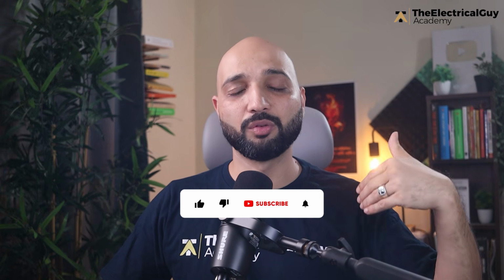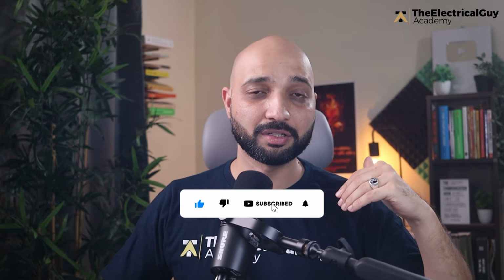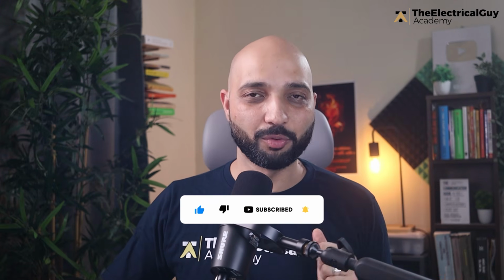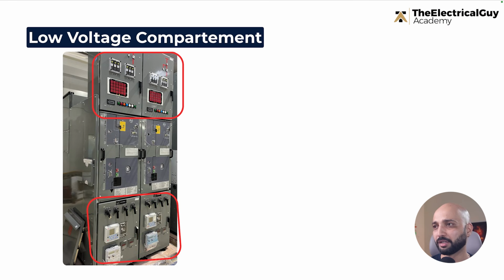So in most cases, the low voltage compartment will be different from one customer to another, one manufacturer to another. In fact, it is even different from one project to another, even if the customer is the same, right? So this may change. There is no standard rule or thumb rule that the low voltage compartment will look like this, or will have only this type of equipment. There is no such limitation. But in this video, I'll try to give you some of the common components that you find in the low voltage compartment, right? So that's the location of the low voltage compartment.